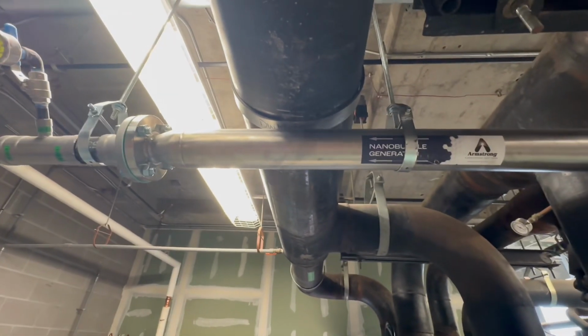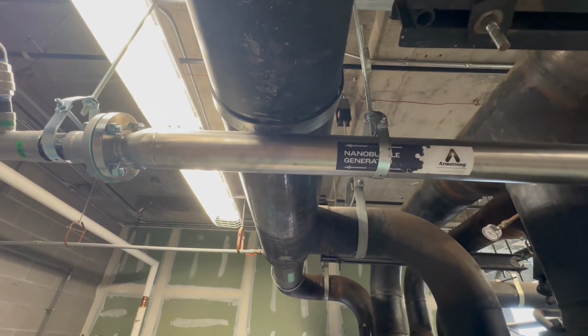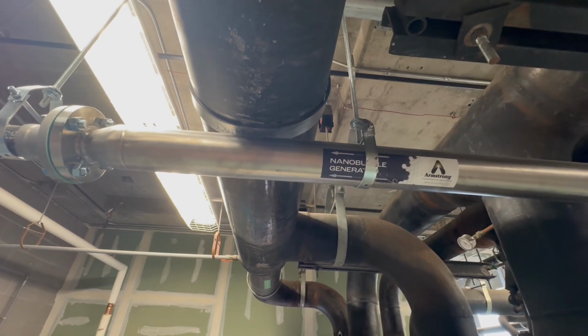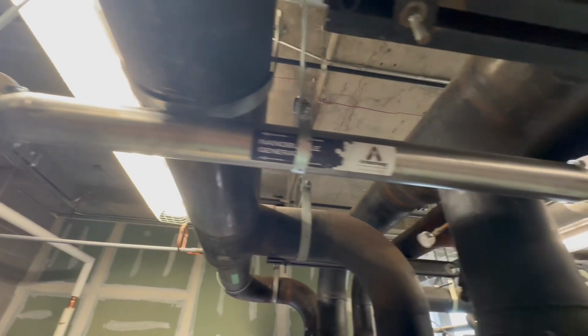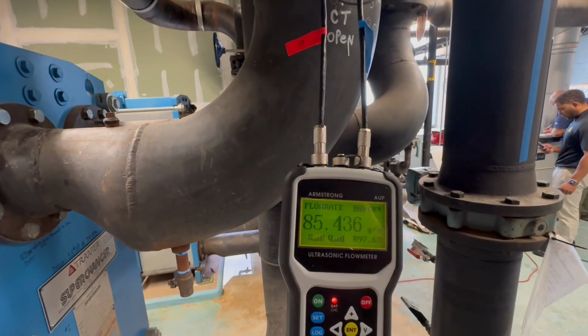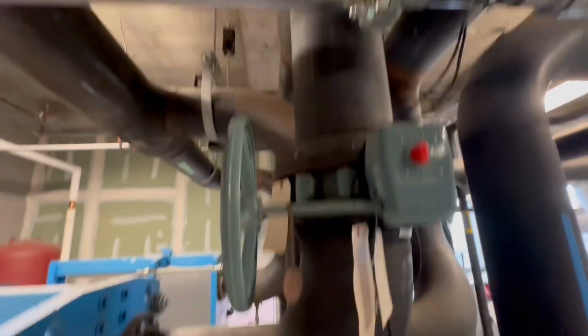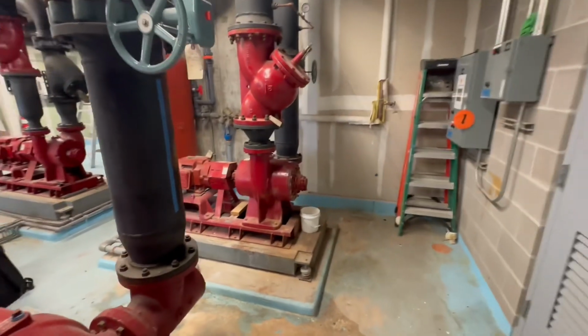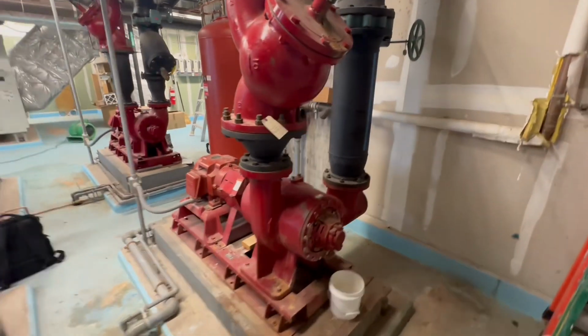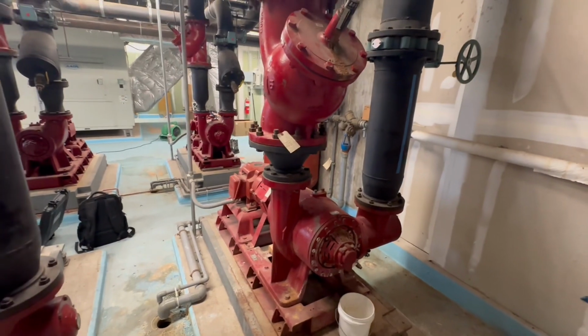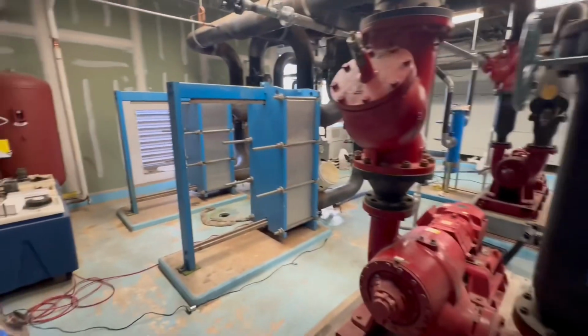Okay, so what we got here is a nanobubble generator installed on a condenser water system at a condominium complex. So it's a 2-inch nanobubble generator running at 85 gallons per minute. The way this system works is that we have our condenser water pumps right here that are circulating water from a cooling tower, which sits on the roof, over to a plate and frame heat exchanger.